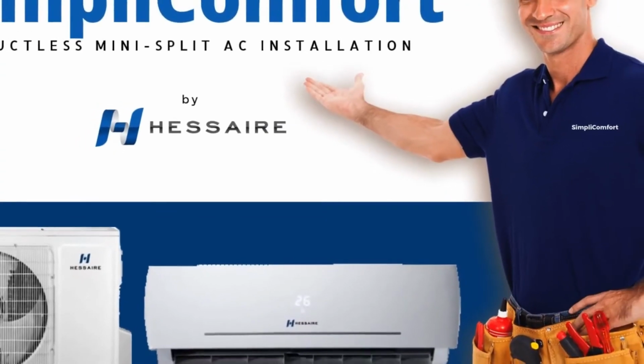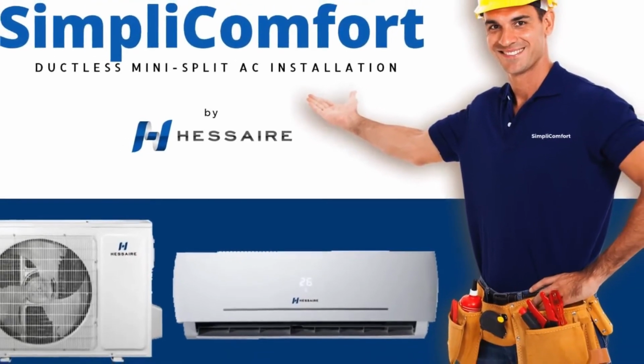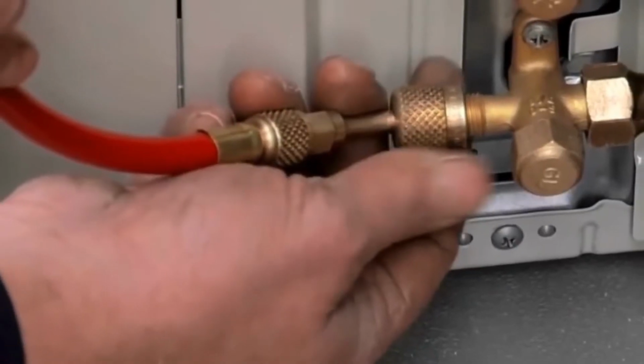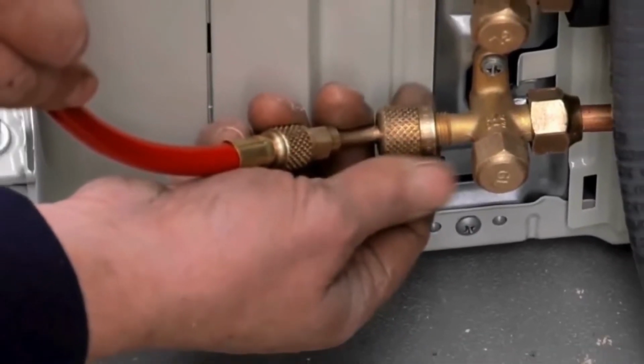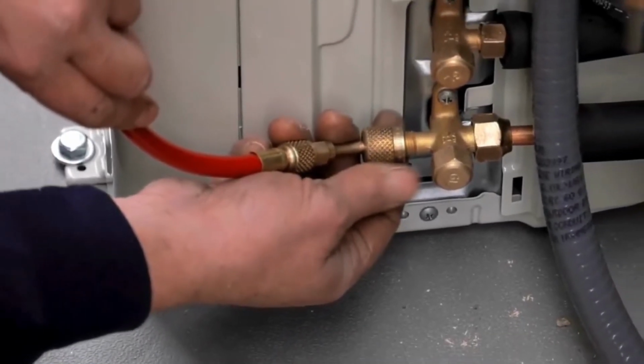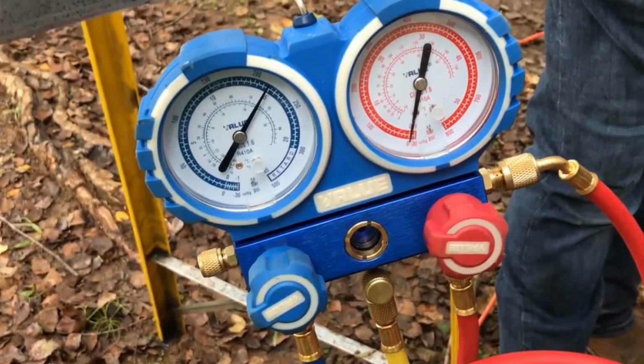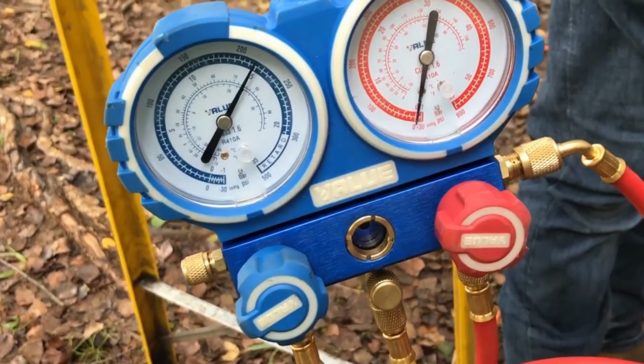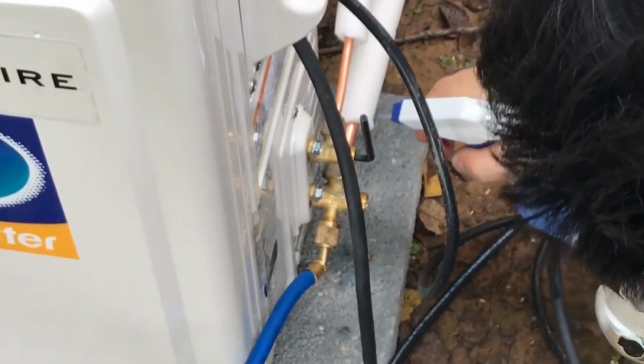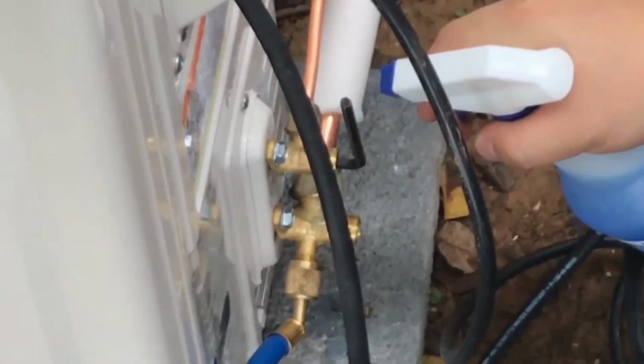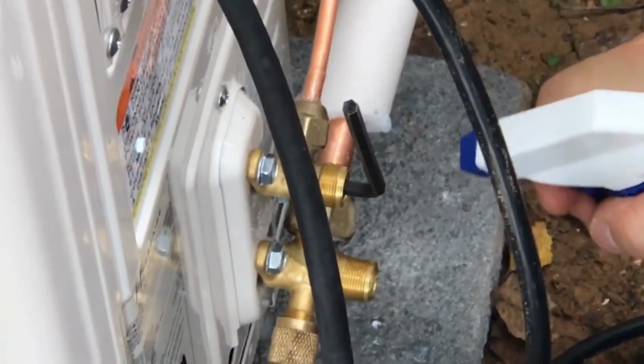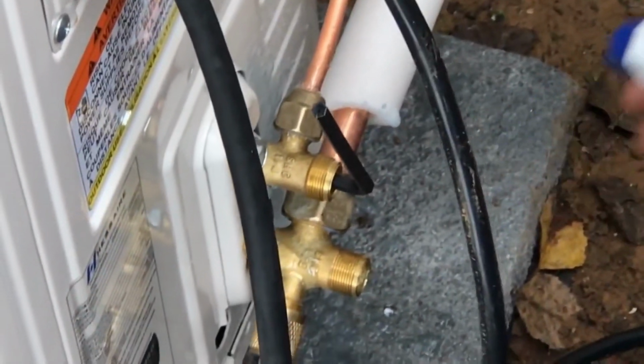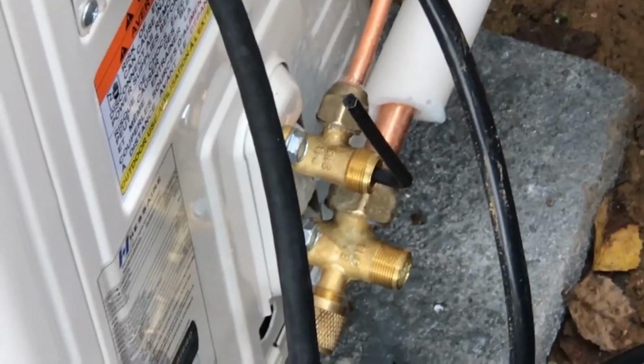A trained professional is recommended to complete the installation at this point. The refrigerant system must be completely sealed in order for the system to perform properly. Start with a pressure test to check for leaks. Then, using a soap bubble solution, spray down all of the flare joints and watch for bubbles to appear. If bubbles are present, tighten the union nut.